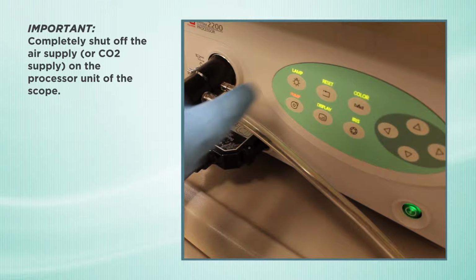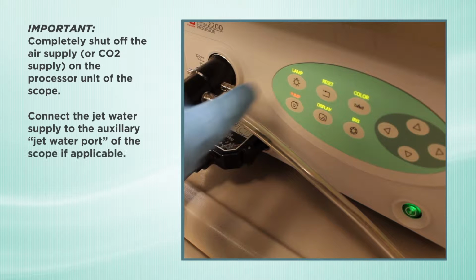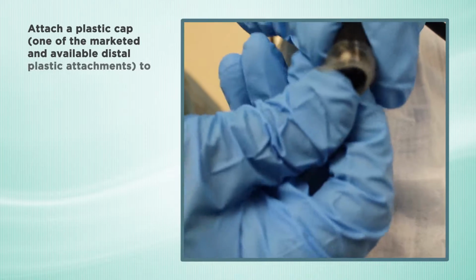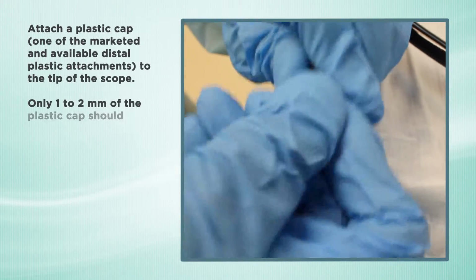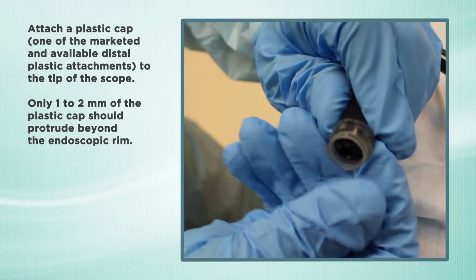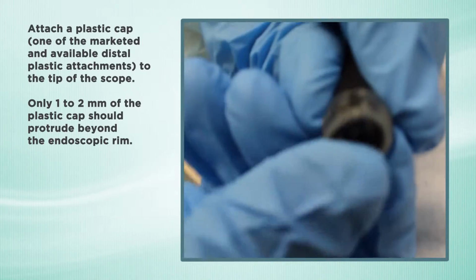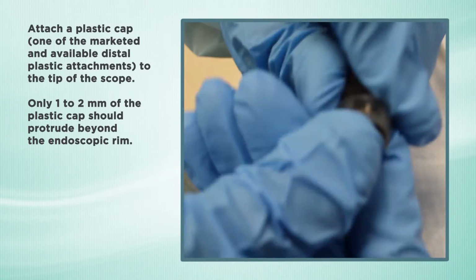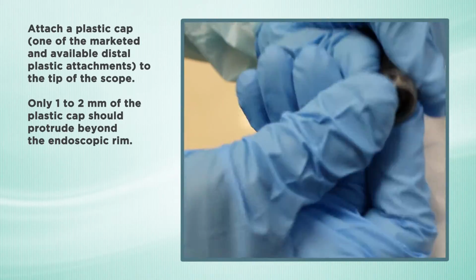Important. Completely shut off the air supply, or CO2 supply, on the processor unit of the scope. Connect the jet water supply to the auxiliary jet water port of the scope if applicable. Attach a plastic cap, one of the marketed and available distal plastic attachments, to the tip of the scope. Only 1 to 2 mm of the plastic cap should protrude beyond the endoscopic rim.